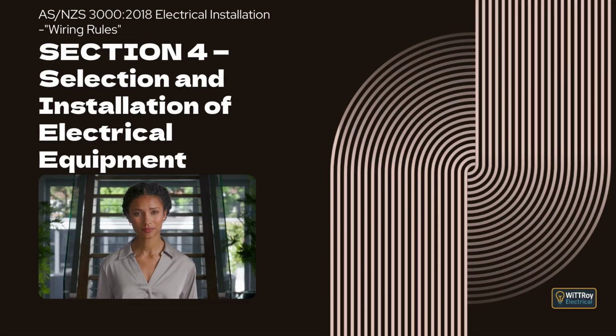Clause 4.12.6 Earthing. This clause explains that the output of an electricity converter must use the same earthing system as the associated installation. It explains that protective earthing conductors must not be switched and that critical protective connections, including the MEN connection, must remain intact whenever the converter is supplying the installation.